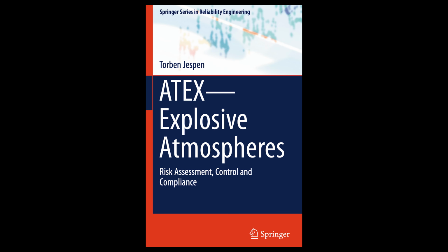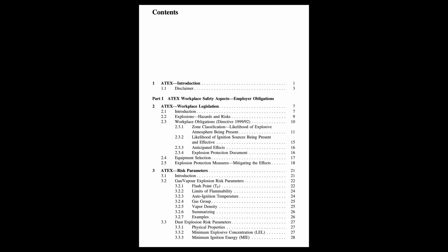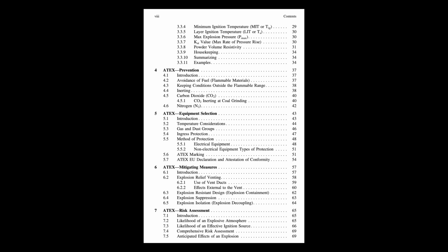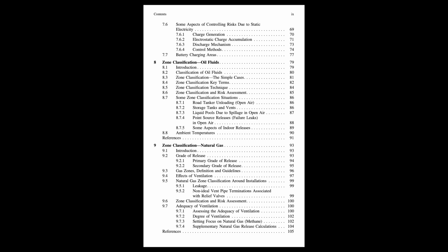What are some common scenarios for this charge buildup? The guide highlights several. Liquids flowing in pipes, especially non-conductive liquids, being poured, stirred, sprayed, or even just settling in a tank can generate charge. People walking around can build up significant charge, particularly if they have insulating footwear on an insulating floor. A person could easily generate a spark energetic enough to ignite common solvents. Just by walking? Yes, potentially thousands of volts. Bulk liquids filling tanks, especially if the flow is turbulent or splashing occurs, is a classic source. Powders being conveyed, sieved, or milled, the amount of charge often relates to how much work is done on the material. Handling low MIE powders in plastic containers or bags is a major concern because the plastic insulates and allows charge to accumulate on the powder. Even mists and dust clouds themselves can become highly charged.